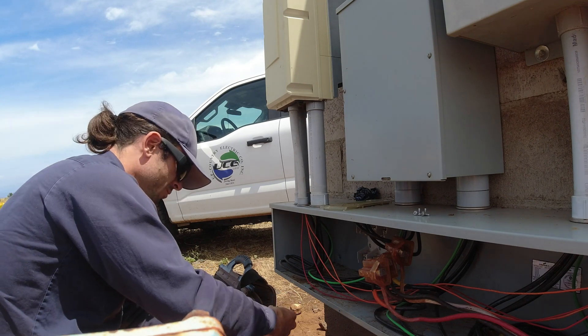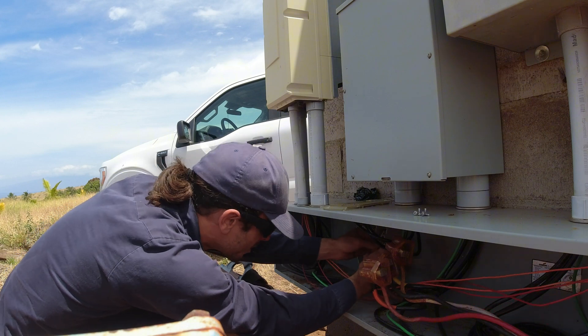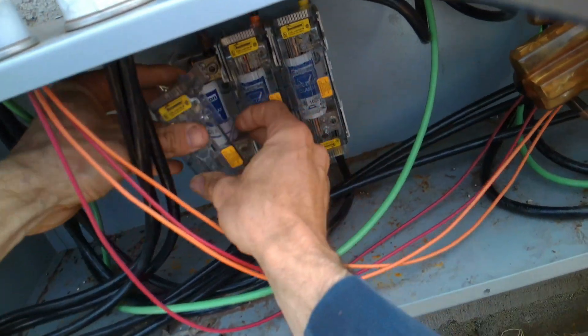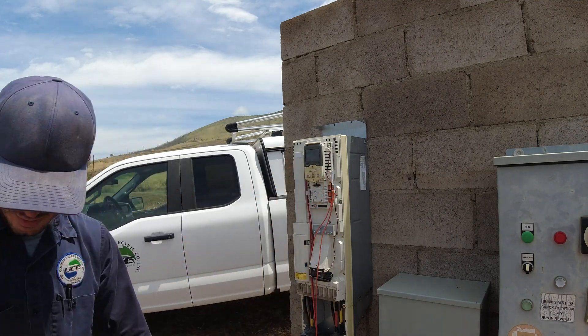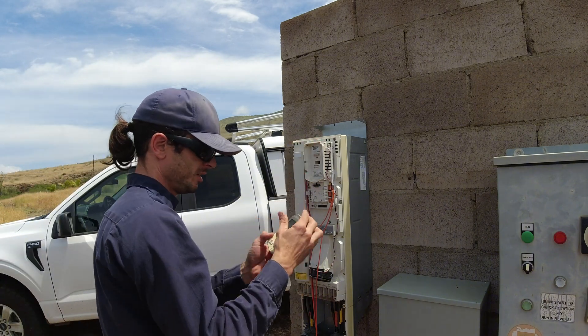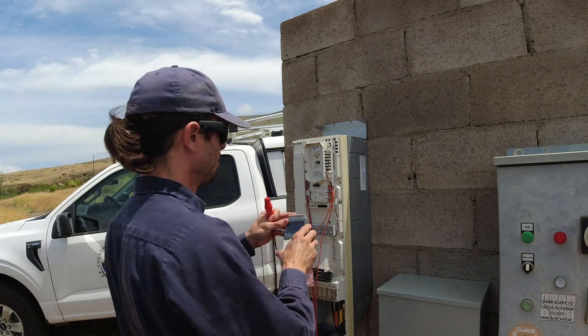Here are our bad fuses and our new ones - Class J JDL, identical. Those are the old ones with the X's on them. We can pop in the new fuses - there we go. And the broken hinges and our old touchpad - blank. We'll save it though, it might still be good. And here's our new touchpad.